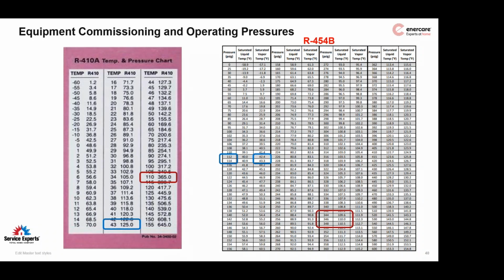So it wasn't as prominent or as drastic, so it didn't really have to be charted to the point where it could affect what you're really seeing for subcooling and superheat when you're taking your measurements, when you're doing your commissioning specifically, or when guys are doing service work. But R454B is different. If you're taking a superheat measurement and you're going to compare it to a gauge temperature or pressure, saturated condensing temperature or saturated suction temperature, you've got to make sure you're using the appropriate column on the chart. When you're on the suction line, you're going to use vapor, and when you're measuring the liquid line, you're going to use the liquid temperature column. So just something that is one of the minor differences to be aware of. Not a huge deal, but a minor difference.